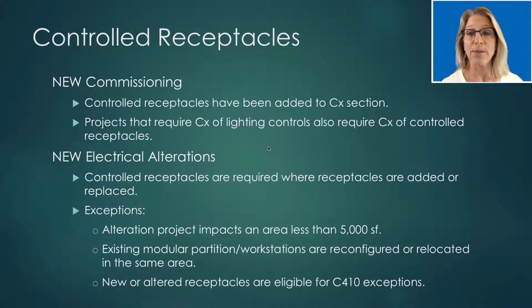There is also language about controlled receptacles in Chapter 5 for existing building alterations. It now states that controlled receptacles are required where the receptacles are added or replaced. There are, however, several exceptions to this requirement. If the alteration project impacts an area less than 5,000 square feet, then controlled receptacles are not required. Also, if the project involves existing modular workstations or cubicles that are reconfigured or relocated within the same area, then controlled receptacles would not be required in that case as well.